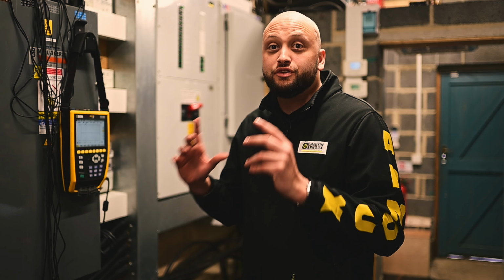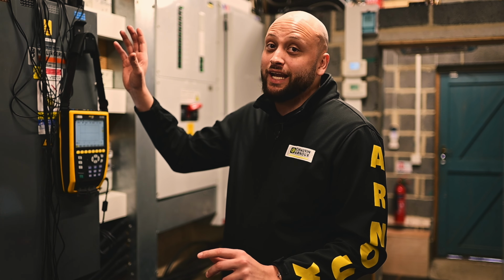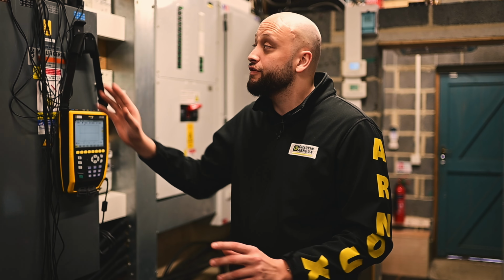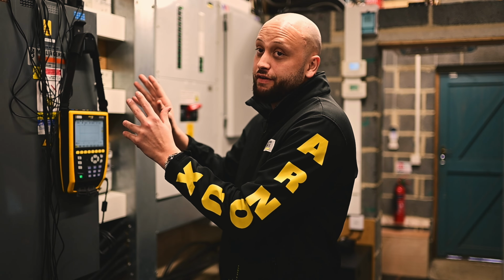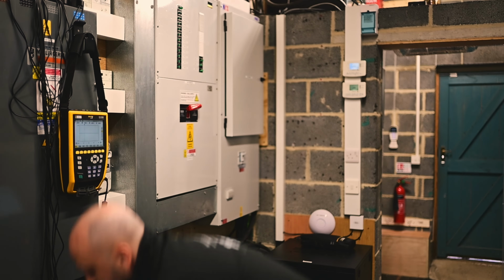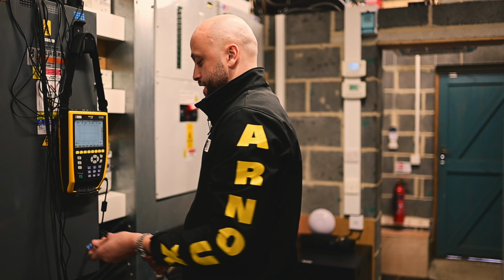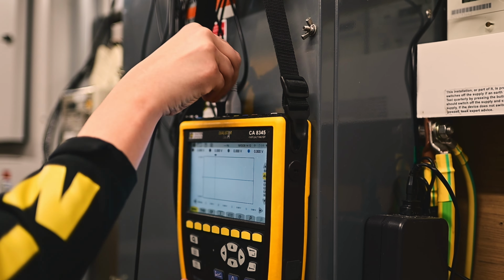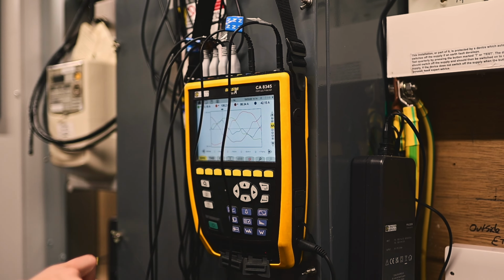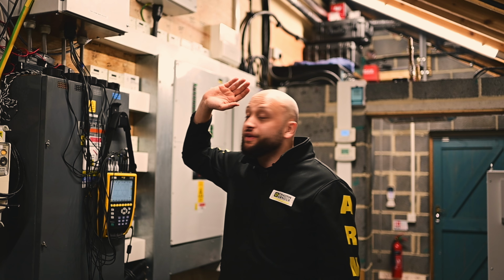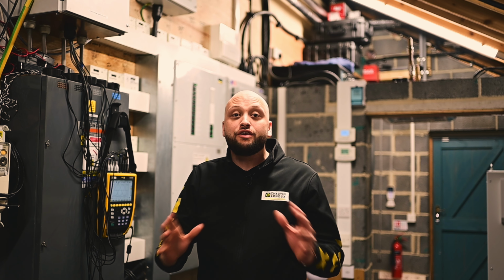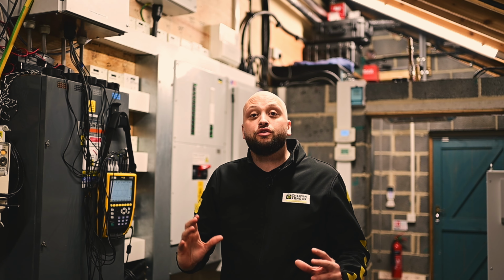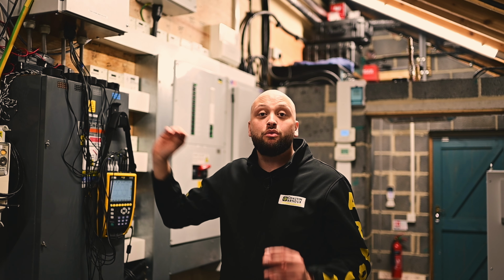We've wrapped the CTs between the main isolator switch and the fuses themselves, which are fused by 315 amp fuses. So we're going to plug everything in, all the CTs into each phase. We've attached all the voltage leads and CTs on this main isolator, between there and the fuses, with 315 amp protection on the fuse side. They're all attached now and we're ready to connect them.